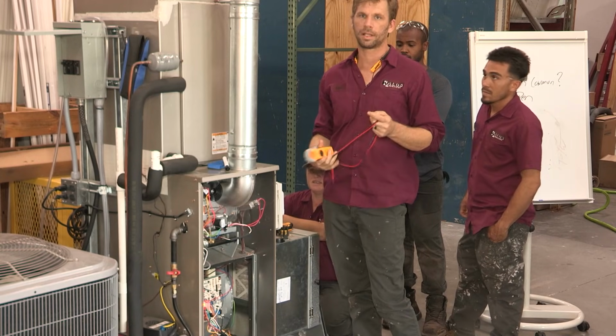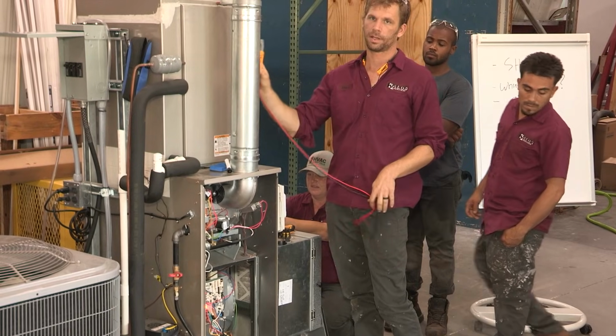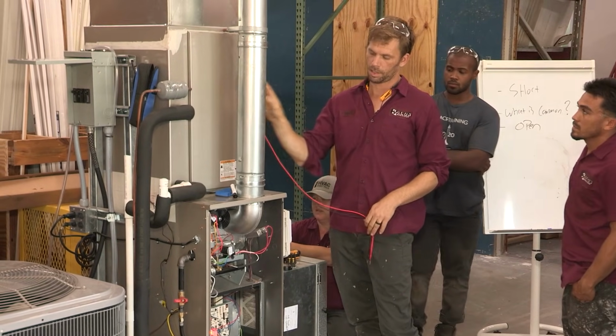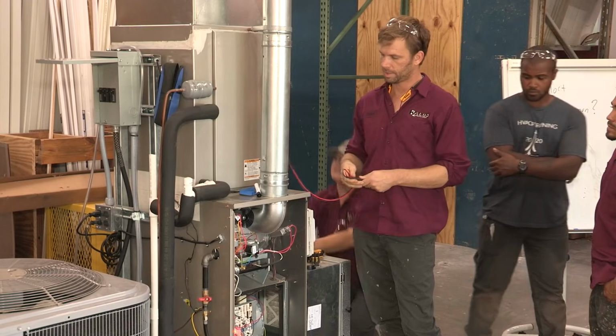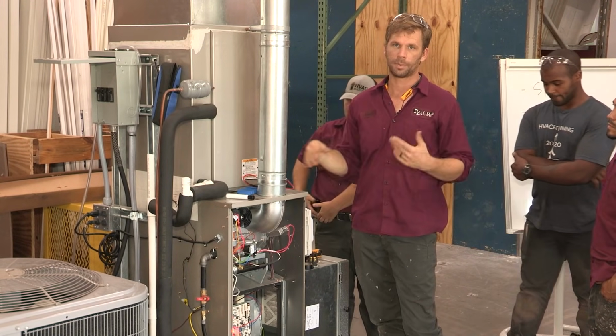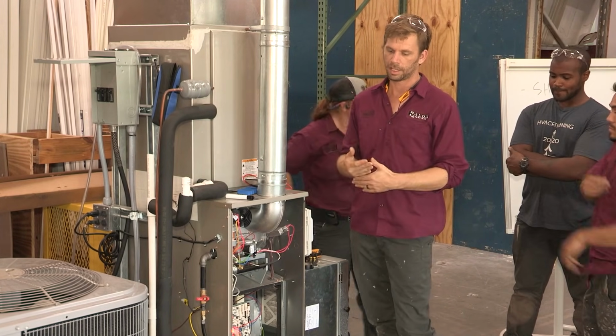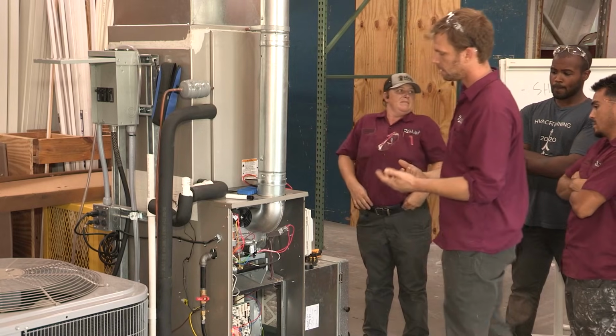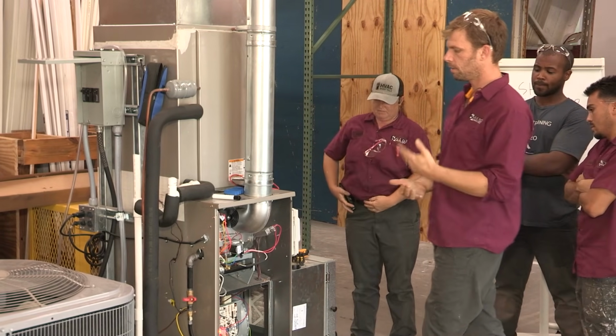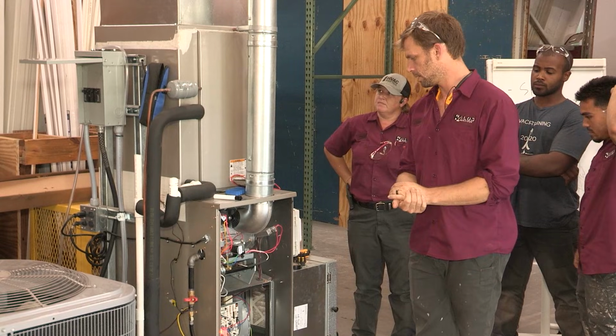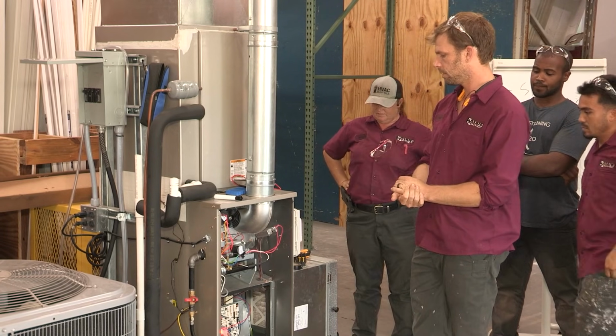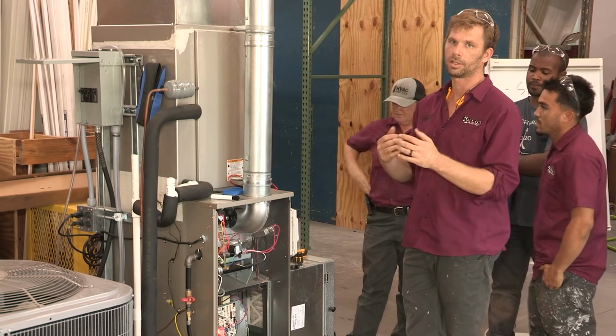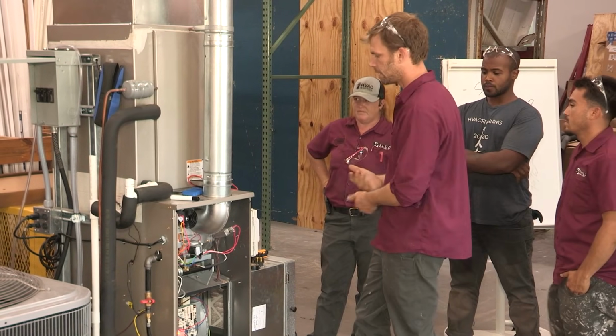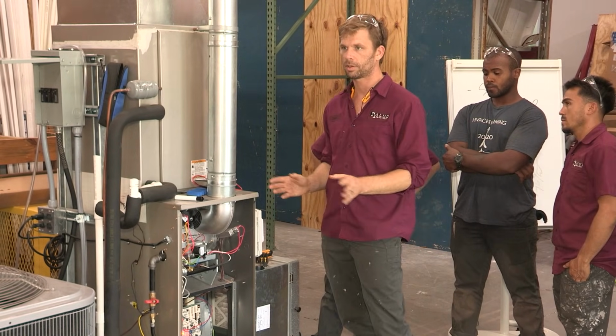To save time, because we can't immediately find this model online, we're just going to bypass the thermostat, because what's happening is that the time delay just keeps repeating. So we've got something causing a short in the thermostat, or an overcurrent, or the thermostat is experiencing too much load and it's just resetting the time delay. We're just going to bypass the thermostat to try to figure out what the problem is.